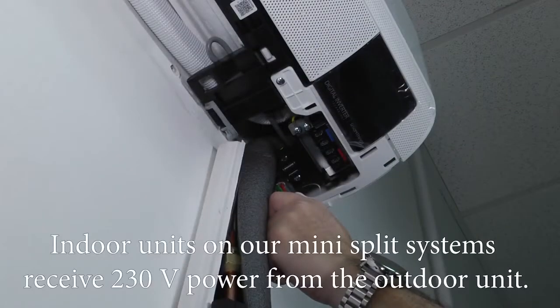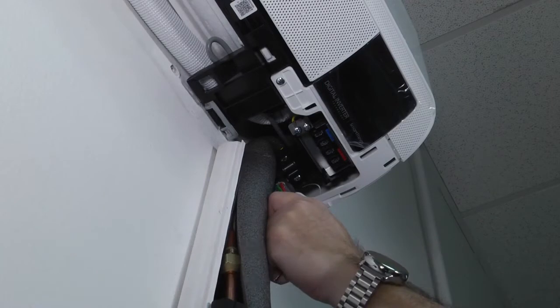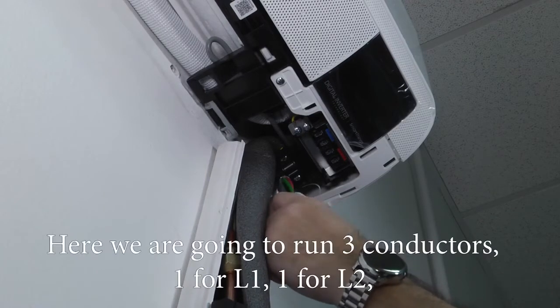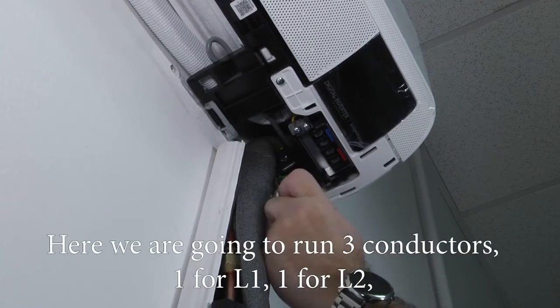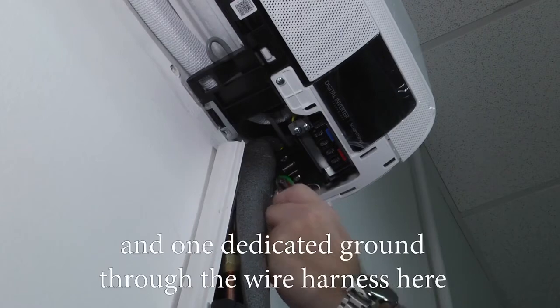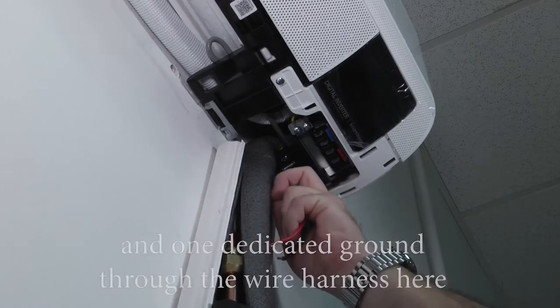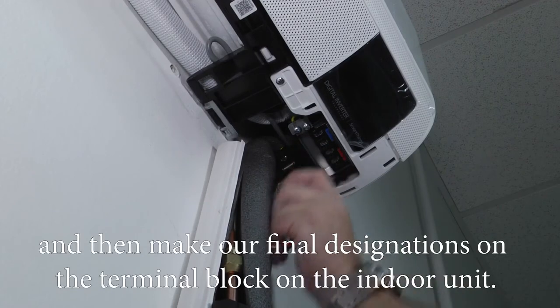Indoor units on our mini split systems receive 230 volts power from the outdoor unit. Here we're going to run 3 conductors, one for L1, one for L2, and one dedicated ground, through the wire harness here, and then make our final designations on the terminal block on the indoor unit.